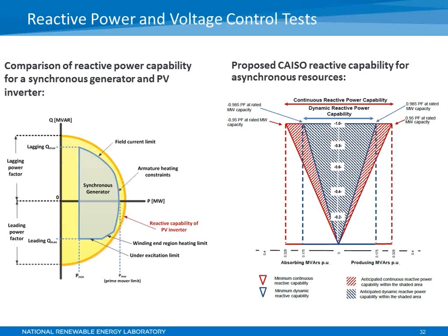Conventional synchronous generators of power plants have reactive power capability that is typically described as a D curve, shown on the left of this slide. The reactive power capability of conventional power plants is limited by many factors, of course, including thermal limits, max and minimum load capability, and also stability limits. And the ability to provide reactive power at zero load is usually not possible for many large plant designs unless it's designed to operate as a synchronous condenser.